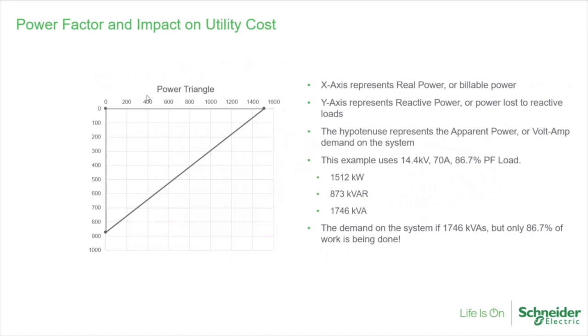So the next thing I was going to talk about is the power factor and the impact on utility cost. When you're looking at your power triangle, the x-axis represents real power, or your billable power. I'm not aware of any customers that are billed on either volt-amps or reactive power. I have seen some customers at AEP may have had a kVA peak demand, more or less ensuring they don't go over a certain amount of demand every 30 minutes. And then the hypotenuse represents the apparent power, or the volt-amp demand on the system.